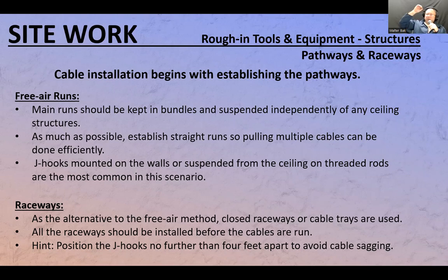People would just go, okay, run the wires. I'm just going to lift them up a little bit. So we're going to strap tie them to those rods, and so they are not laying on the ceiling tiles. That used to be the practice, but later on, people were told not to do that. Every cable run should have independent suspension from any other ceiling structure.